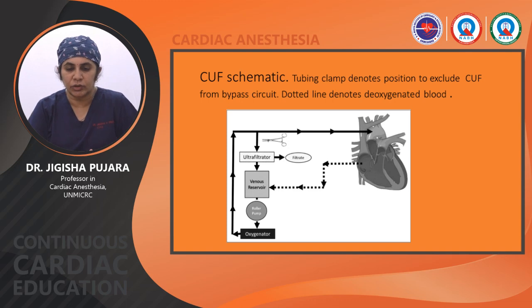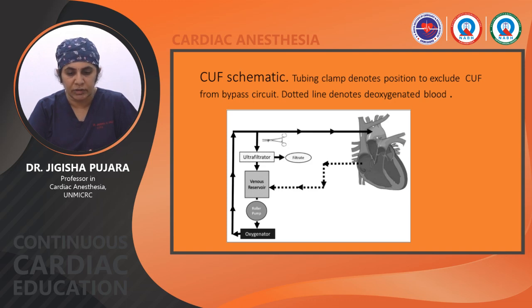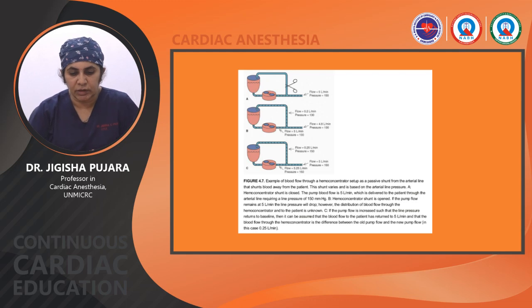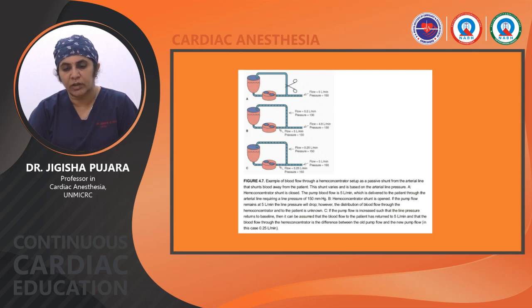This limitation necessitates intermittent use of CUF, slows the rate of volume removal, and requires additional fluid to the CPB circuit, which can be counterproductive. The schematic diagram shows: tubing clamp position to exclude the CUF from the bypass circuit, dotted line denotes deoxygenated blood. Blood from the venous reservoir passes through the roller pump and oxygenator; when ultrafiltration is used, the clamp opens and blood passes through the ultrafiltrator. To maintain continuous volume, fluid must be added up to baseline pressure so that the filter does not cause hypovolemia.